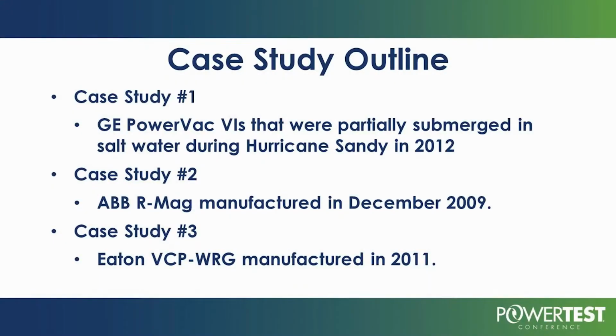We have a few case studies here we're going to talk about now, things that we've done in the field. We've done hundreds and actually we've done thousands of interrupters, but we're just going to highlight a few. One of them here is a set of power vac interrupters that came out of Hurricane Sandy in 2012, and we started conditioning them in 2012, 9 years ago. So we've watched them twice a year for 9 years and measured the pressure, measured the ion current, which essentially relates to pressure. And in that, we've watched these interrupters over a period of 9 years.